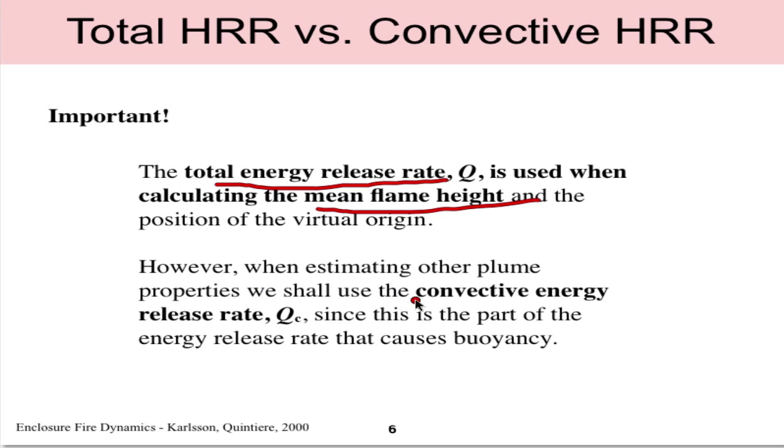Otherwise when we estimate other plume properties we'll use Qc which is the convective heat release rate. Typically for most fires and for this course we will assume that the convective energy release rate is 70 percent of the total heat release rate and this is true for liquid pool fires and most cases.